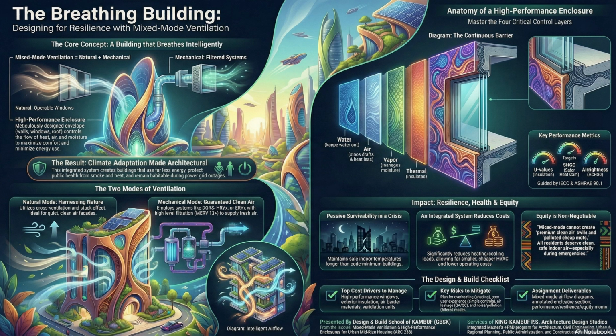But when conditions force us into that red zone, we have to rely on the machines. And the source material highlights some specific high-performance technologies for that. Yeah, the key shift in modern design is separating your air conditioning from your ventilation. For ventilation, we now rely on a DOAS, which is a dedicated outdoor air system. How is that different from a traditional AC unit? Well, traditional AC often just cools and recirculates the interior air, and it only brings in a tiny bit of fresh air from outside. A DOAS supplies 100% fresh, fully conditioned, so that's heated, cooled, dehumidified, and filtered outdoor air. And it does that independently of the system that handles the room level temperature. So you can guarantee the air is actually fresh and clean. We can guarantee that we're meeting the safe, clean air delivery rates that are mandated by code, no matter what the temperature needs of the room are.